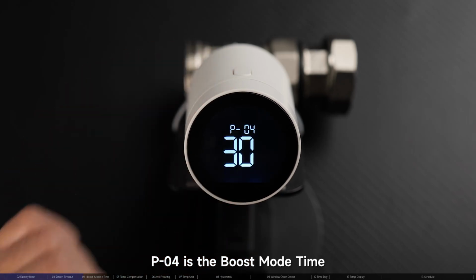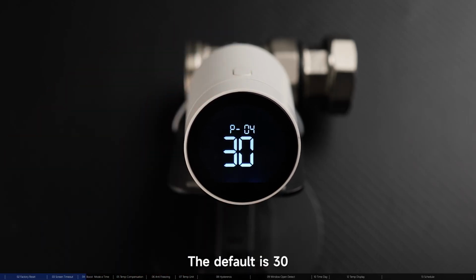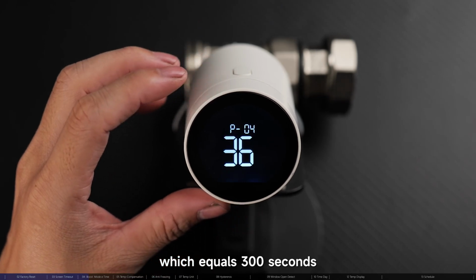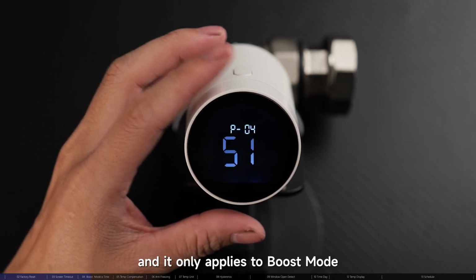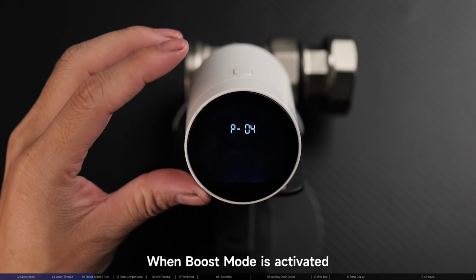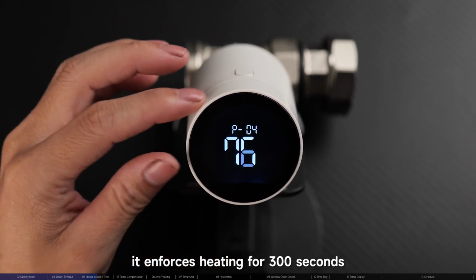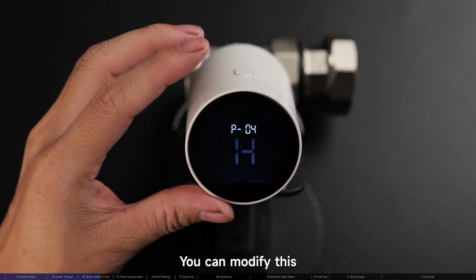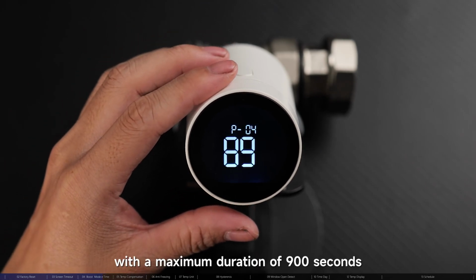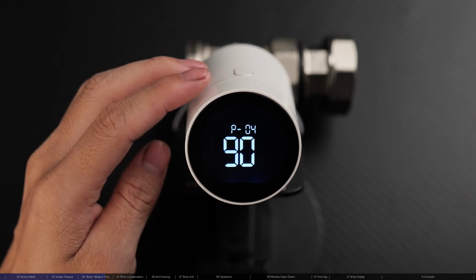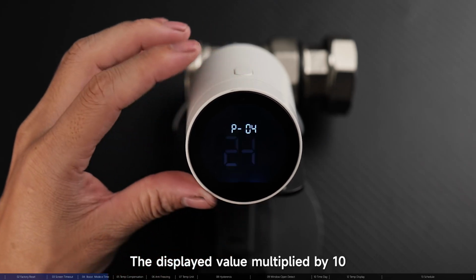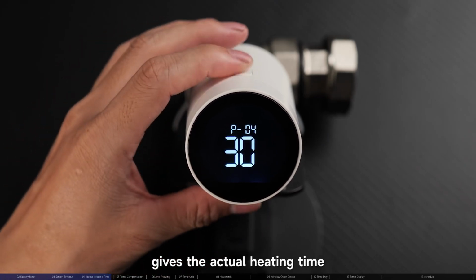P04 is the boost mode time. The default is 30, which equals 300 seconds, and it only applies to boost mode. When boost mode is activated, it enforces heating for 300 seconds. You can modify this with a maximum duration of 900 seconds. The displayed value multiplied by 10 gives the actual heating time.